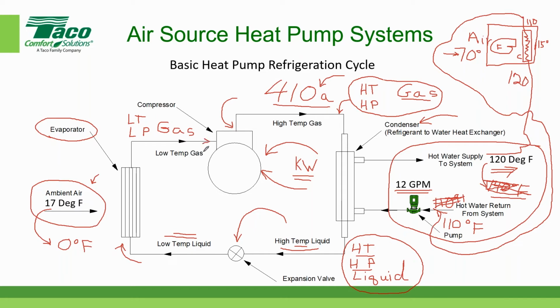If it enters the compressor as a liquid, liquid is incompressible and you could break the compressor. So therefore, we have to have enough surface area in the evaporator to ensure that the refrigerant leaves the evaporator as a superheated gas, so slightly above the saturation temperature. And the way we do that is by putting a temperature sensor right here and then connecting that to a modulating expansion valve down here. And so if the temperature is not high enough to ensure that it's a superheated gas, then the expansion valve will be adjusted accordingly to ensure that we wind up with a gas in the suction side of the compressor. So there we go.